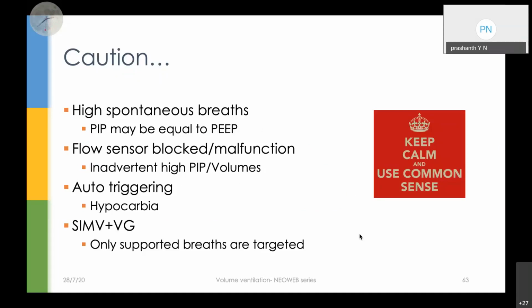So what if there is a block in the flow sensor at that point of time, the flow sensor is not working and the baby's compliance is improving? Since your flow sensor is blocked, the ventilator might give your maximum PIP, not the working PIP, which can be counterproductive. So it can give inadvertent high PIP and volumes in a weaning mode if your flow sensor is not working. We also should be wary of auto triggering, because it can cause hypocarbia. If there is auto triggering, more and more breaths will be targeted, and unnecessarily more minute ventilation will cause hypocarbia in these babies.